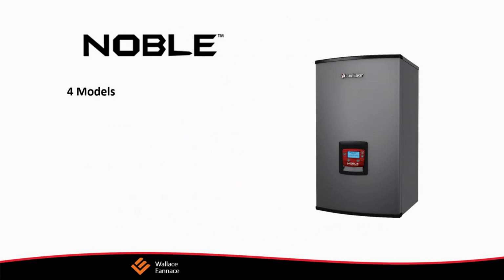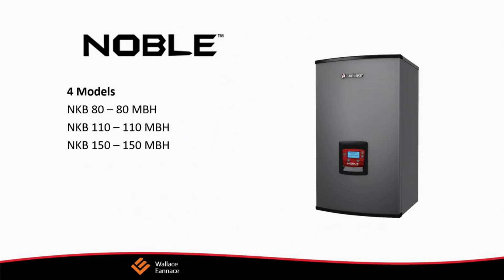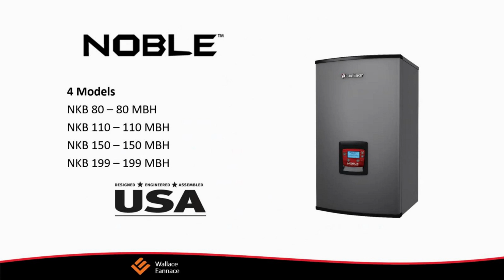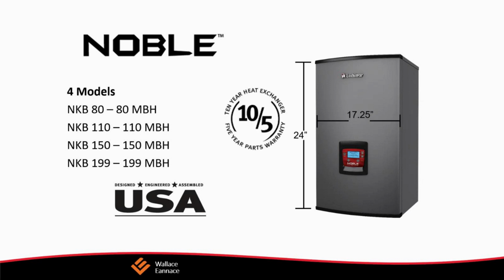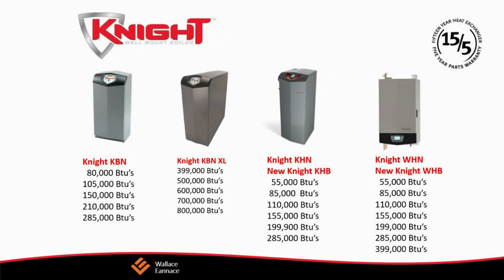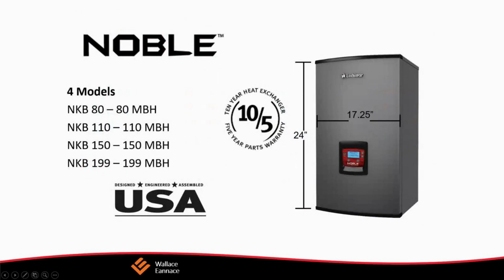And the reality is, when we go back to that bin data a few slides back, most of the time we're going to be in that 35-degree area. We're not going to be at that 0-degree area. So would we choose a 50,000 BTU unit or 100,000? Would we want to put a boiler in? How many boilers do we put in the room? Do we put 2 50s? Do we put them all the same size?